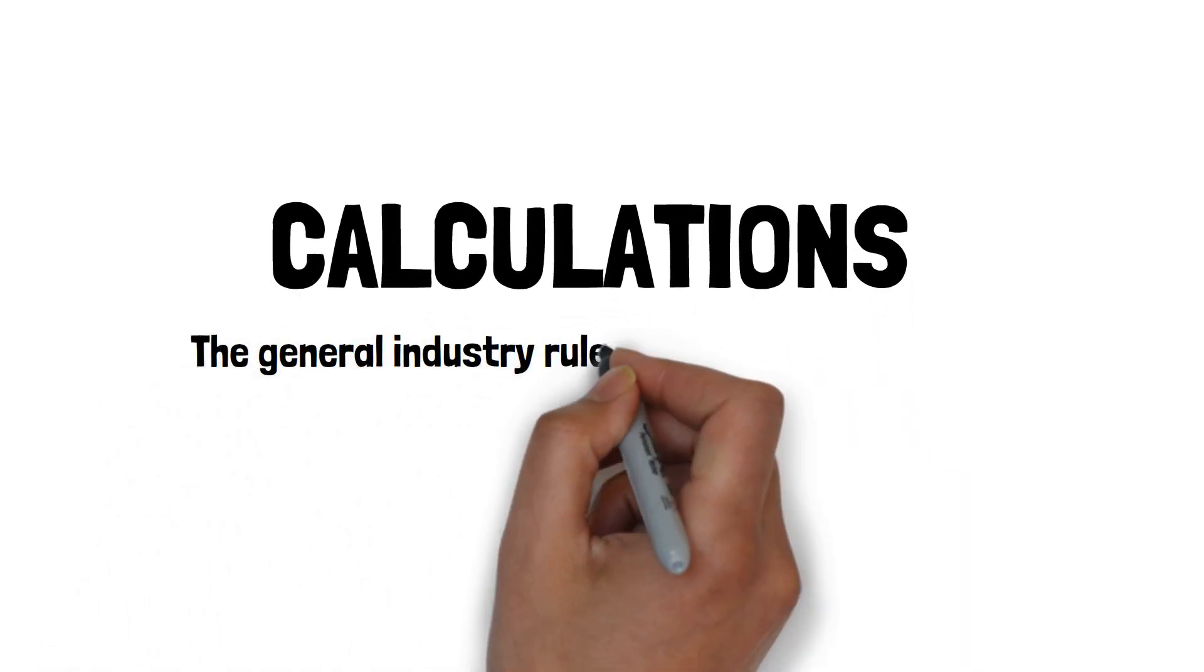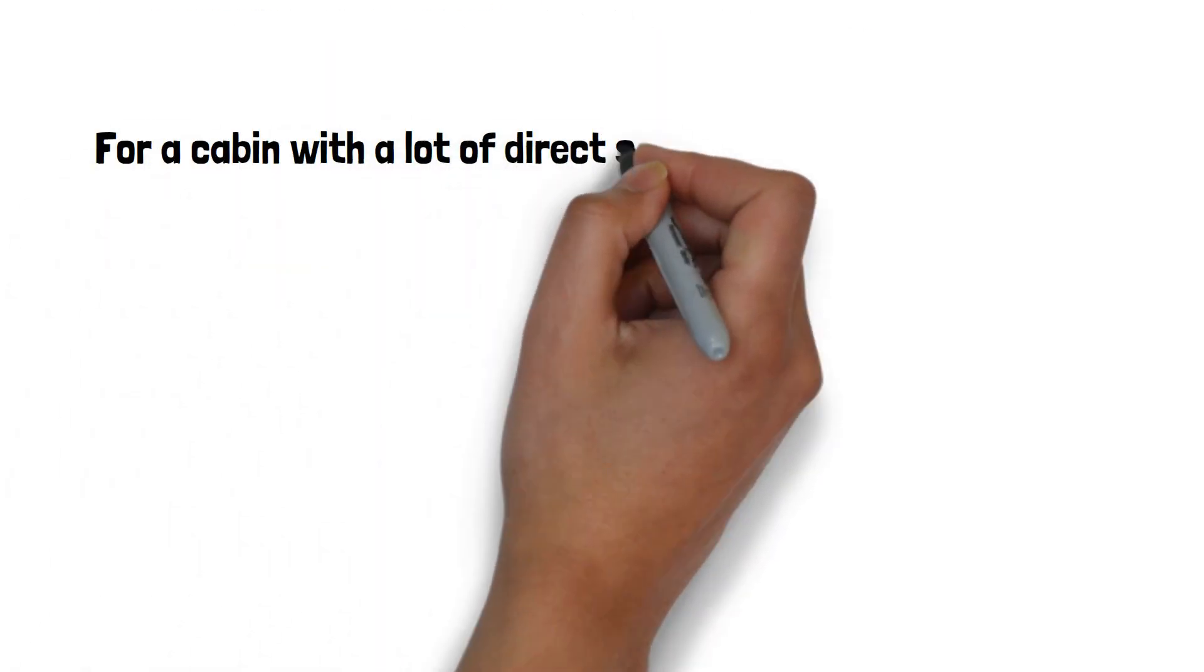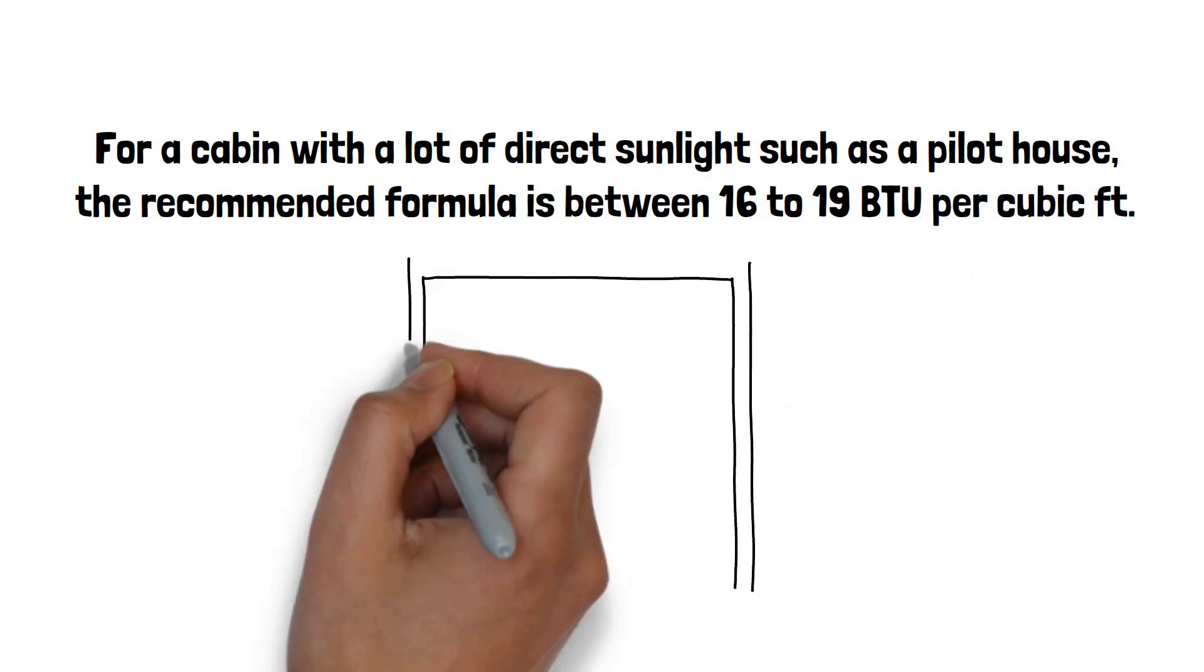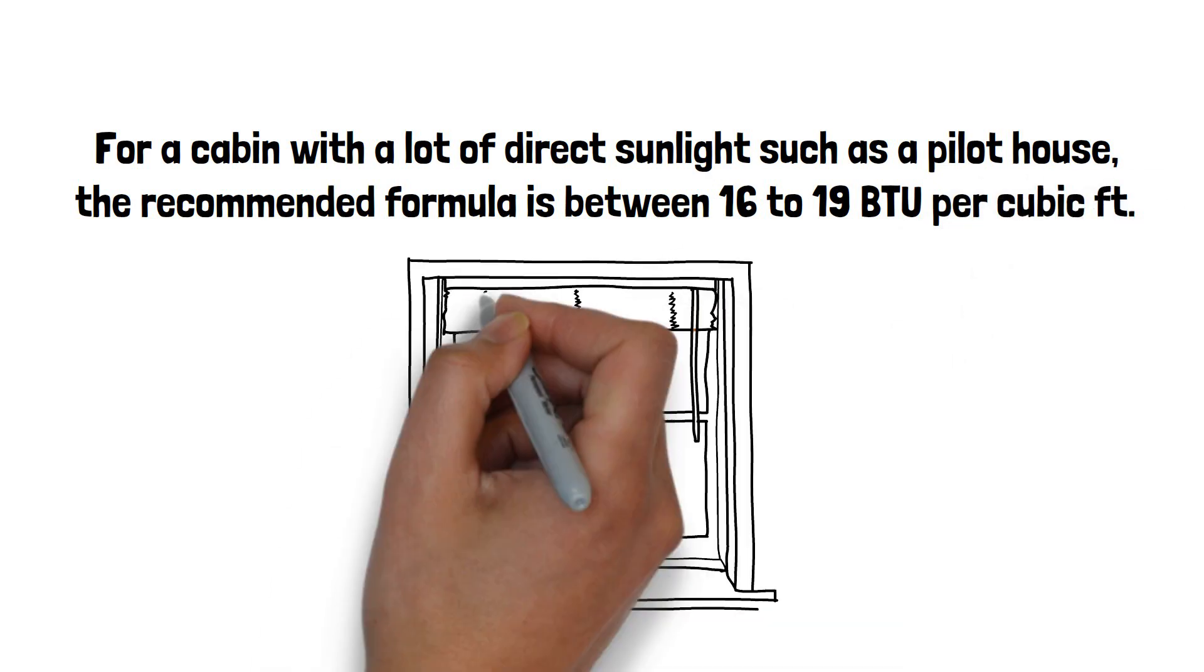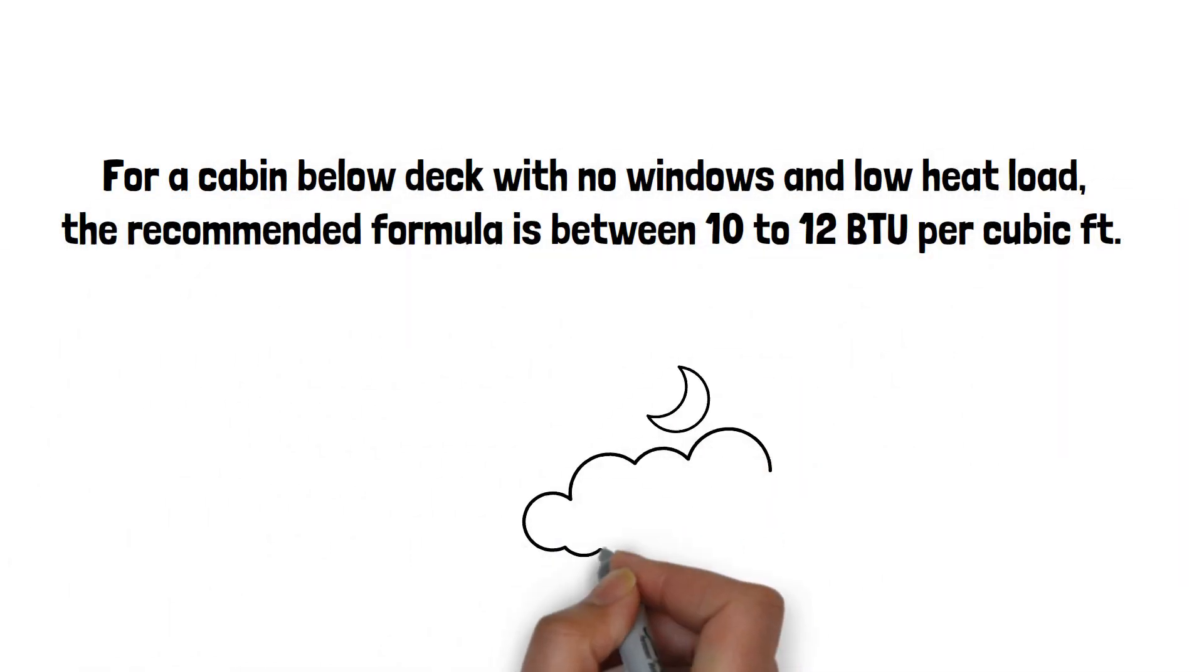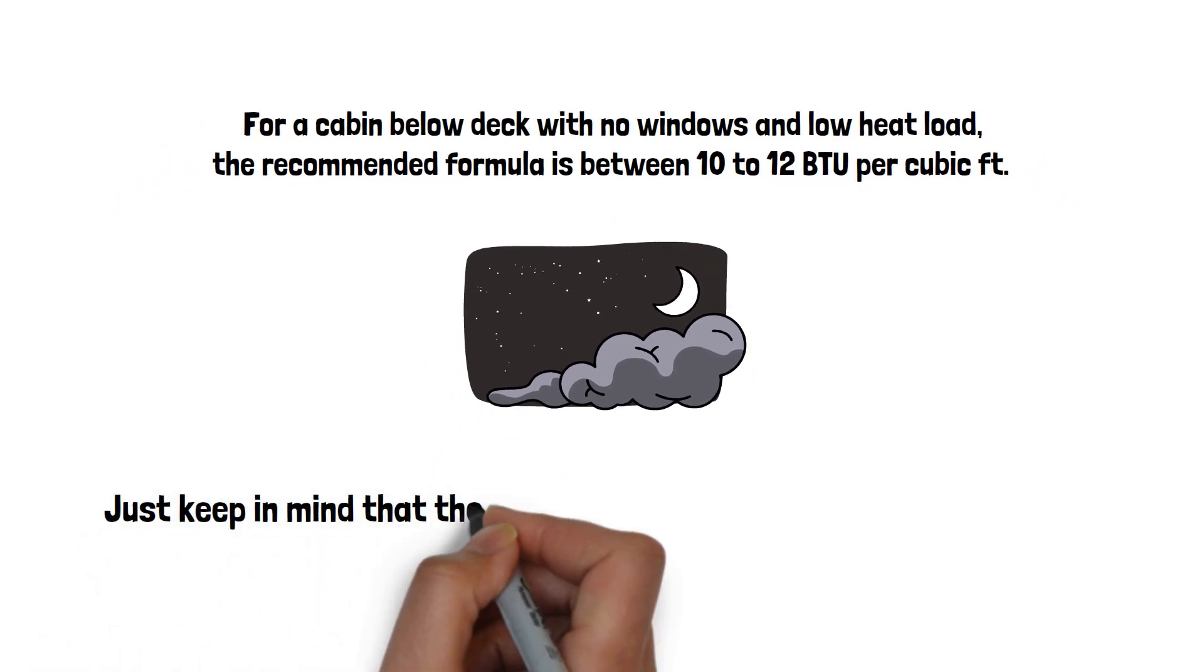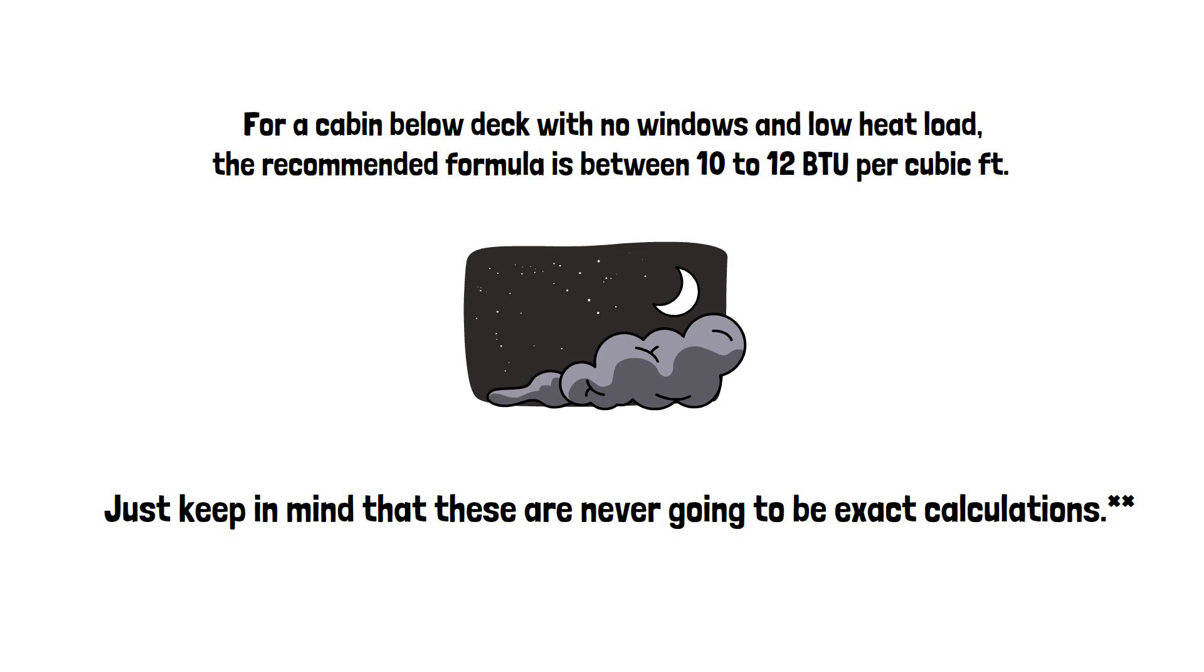Calculations. The general industry rule for sizing an air conditioner is 14 BTU per cubic foot. For a cabin with a lot of direct sunlight such as a pilot house, the recommended formula is between 16 to 19 BTU per cubic foot. For a cabin below deck with no windows and low heat load, the recommended formula is between 10 to 12 BTU per cubic foot. You can use these formulas to determine BTU for your cabin space. Just note that these numbers are usually a generalization and may not be sufficient during the hottest of days. Alternatively, they can also cause oversizing during the coldest of days.